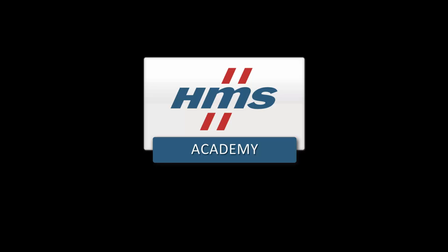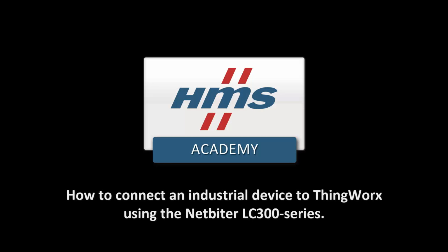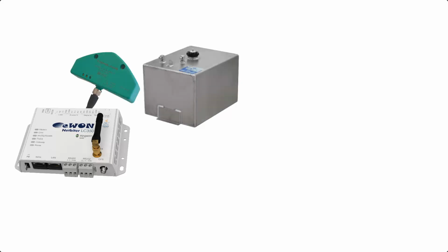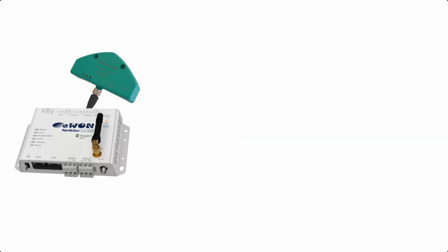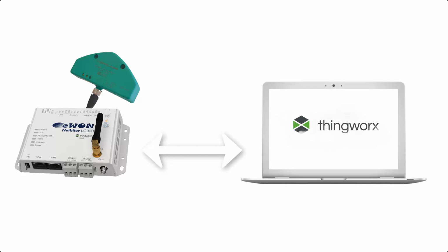In this demo, we will show how to connect an industrial device to ThingWorx using the Netbiter LC300 series. In this scenario, I have connected the Netbiter LC to a Modbus-based tank sensor which measures the levels in a fuel tank. The tank sensor is connected via a serial RS485 cable to the Netbiter. Okay, so let's see how we can get the live Modbus data from the tank sensor over to ThingWorx.